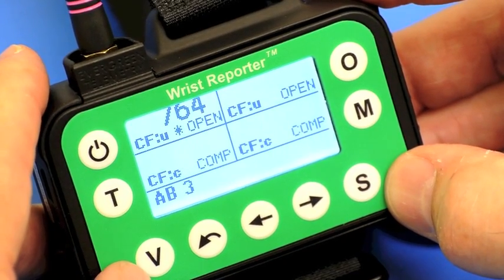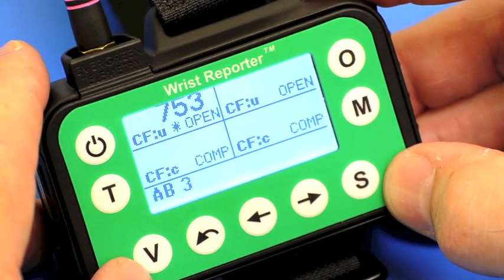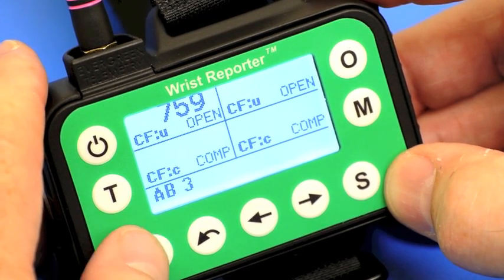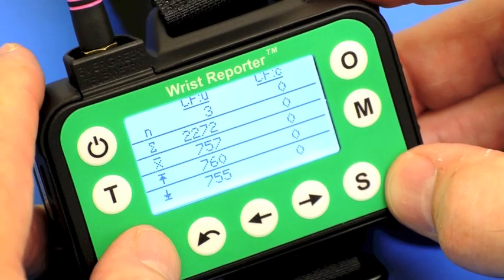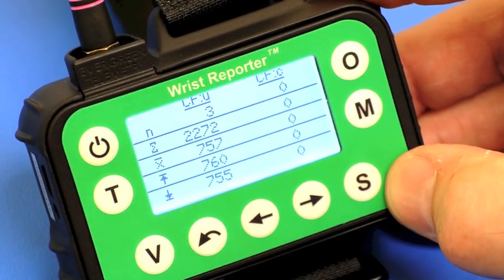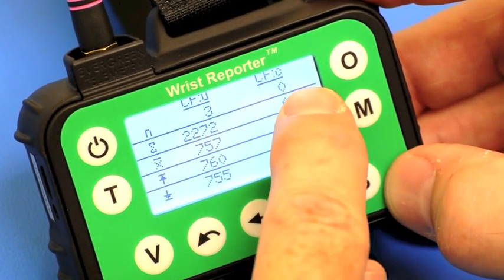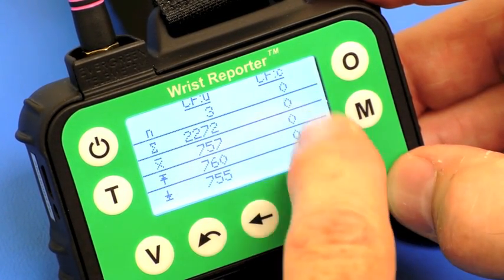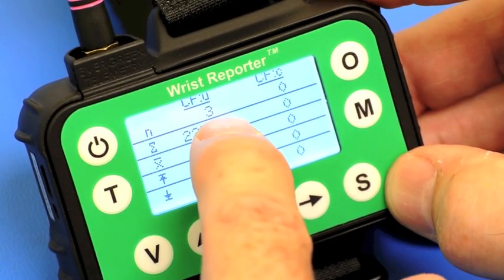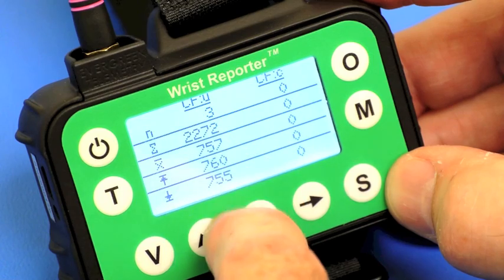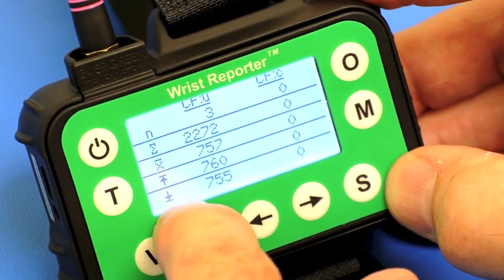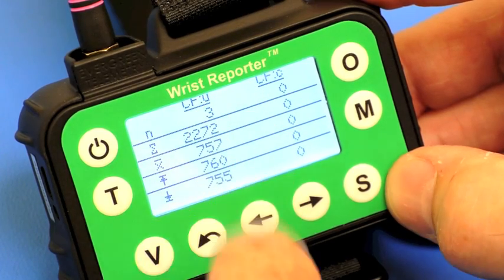Pressing V takes me to a screen that's only used for back pressure compensation — I'll come back to that feature in a minute. In this next window, I can look at the different ways that the statistics can be viewed. There's a column for uncorrected and a column for corrected. I've stored three different readings; this shows the number stored, the sum, the average, the max, and the min of those particular readings.